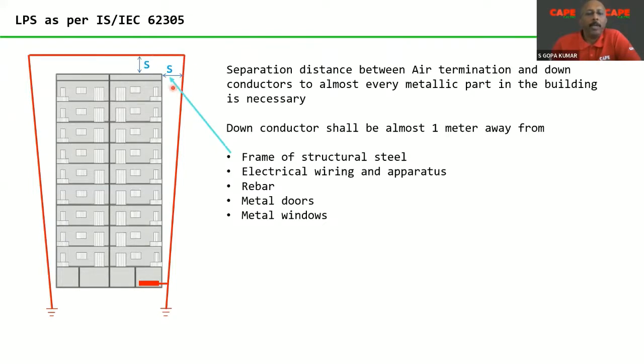Technically speaking, if you are adopting the technique of separation, then you have to calculate the separation distance and keep the air terminal and the down conductor physically away from the building. Away from what? Away from the frame of the structural steel, away from electrical wiring and apparatus, away from rebar, away from metal doors, away from continuously connected metal doors and windows.